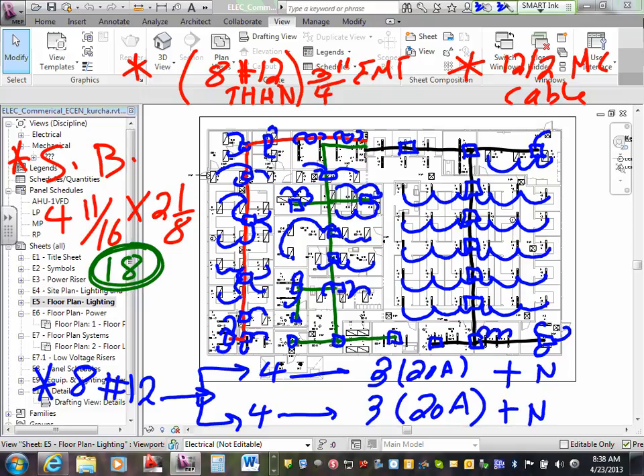You know, you could MC cable from this fixture to this fixture. You can do that to the other fixture, and that will give me 1 MC cable, number 12, that I can land directly into this box. So I got this one. I add another one here. I went fixture to box. Fixture to box, or you can go directly from fixture to the box if you're within 6 feet. So that's how I place my boxes.